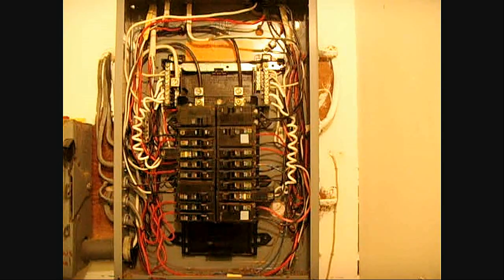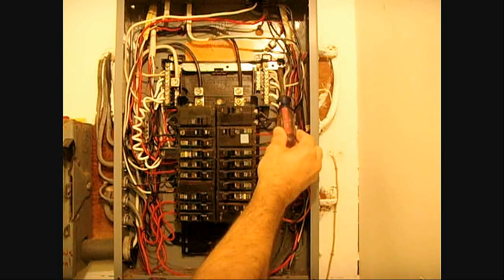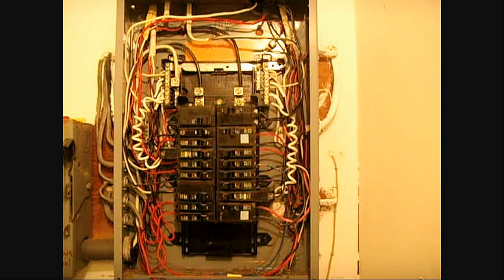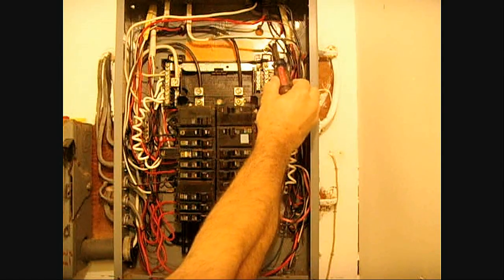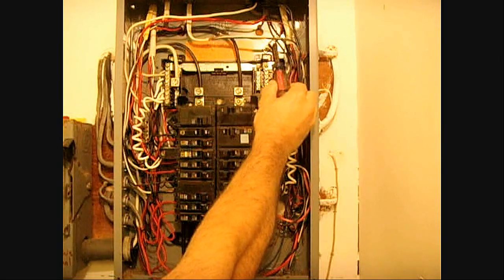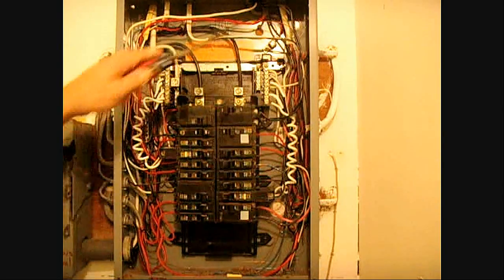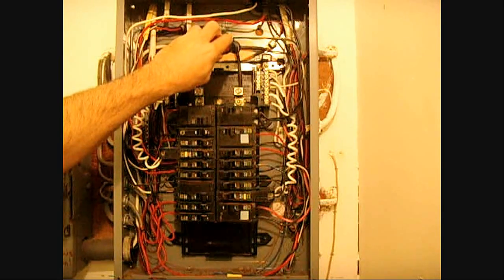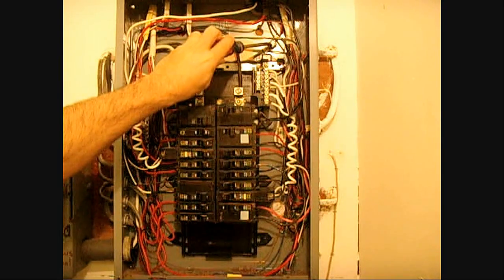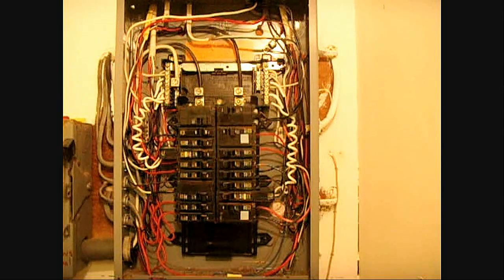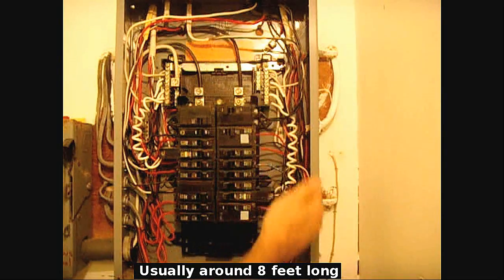If you choose to not bond the panel by placing the screw in here and tightening it down securely, then the next thing you would do is have a separate ground wire, usually a 10 gauge wire, could be a little thicker. In this case, whoever put this panel in didn't have the right color wire, so they took two 14 gauge wires, twisted them together, and it connects right here. It's screwed into the metal enclosure. This wire right here, which is connected to this lug, goes through this cable, and it goes outside the house where it goes onto a clamp on your cold water pipe, or it gets clamped onto a copper rod or a copper clad rod, which is driven into the earth. That makes this whole panel grounded.